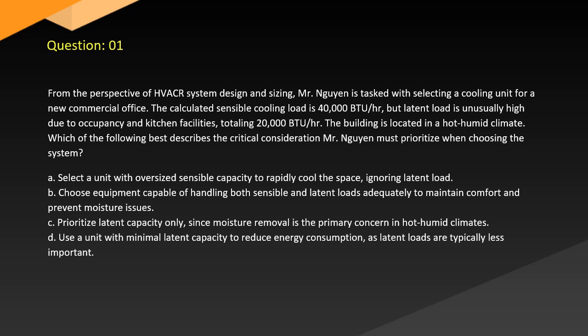Question 1. From the perspective of HVACR system design and sizing, Nguyen is tasked with selecting a cooling unit for a new commercial office. The calculated sensible cooling load is 40,000 BTU, but the latent load is unusually high due to occupancy and kitchen facilities, totaling 20,000 BTU. The building is located in a hot, humid climate. Which of the following best describes the critical consideration Nguyen should prioritize when choosing the system?